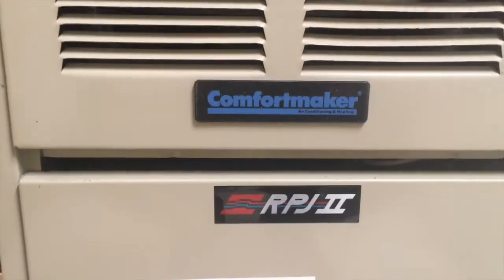Today I'm going to show you how to clean the flame sensor on a Comfortmaker RPJ II furnace, kind of a mid-90s vintage furnace. The issue I'm having with the furnace, and again this is an occasional issue, is that when there's a call for heat from the thermostat, the furnace kicks on, the fan turns on, and it goes through its cycle as it normally would to turn on. But about 3 to 5 seconds after the burner ignites, everything shuts off.